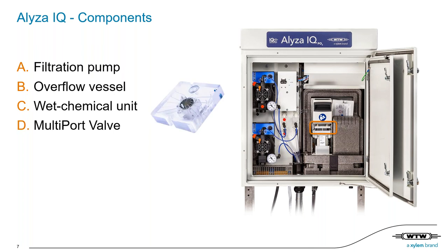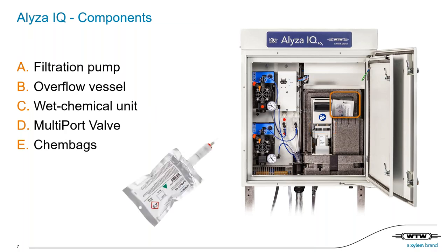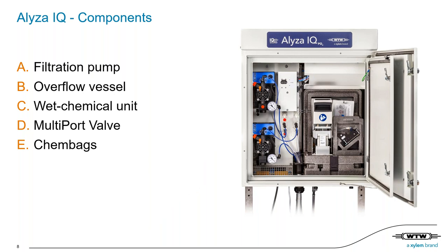Here's the location of the multiport valve, the heart of the analyzer. More on that later. This is the location of the so-called chem bags, which contain the reagents. I'll come to them in a few minutes. And last but not least, the photometric unit, which is in a temperature-controlled compartment at 45 degrees Celsius to help speed up the reaction and increase the measurement accuracy and stability. Now let's go over to the unique components, the multiport valve and the chem bags.